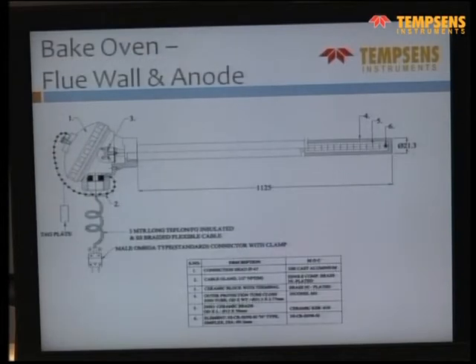For carbon, they make carbon anodes in the primary aluminum plant. In this case, they are using Inconel 601, and inside is an N type bare element. They had the same problem of the green rot effect and all those things. So they have shifted to Inconel 601 and an N type bare element of 3.2 millimeters. At this moment, I'm happy to say this. I'm the customer who had asked for the requirement and it has been started. Now you're not having that problem.